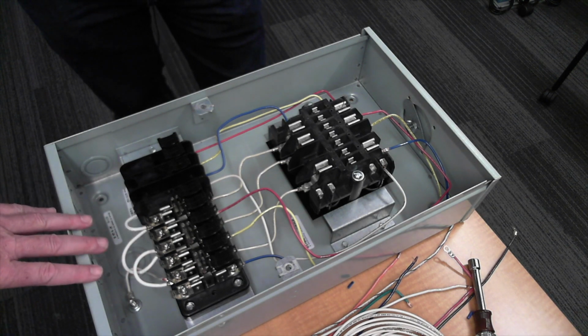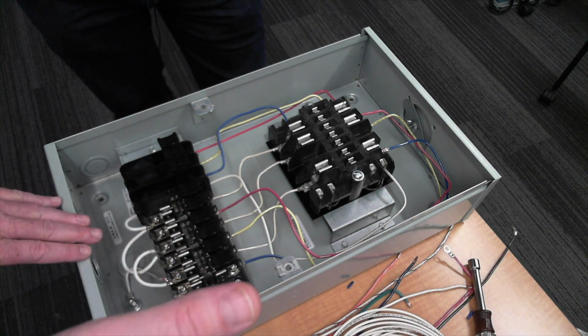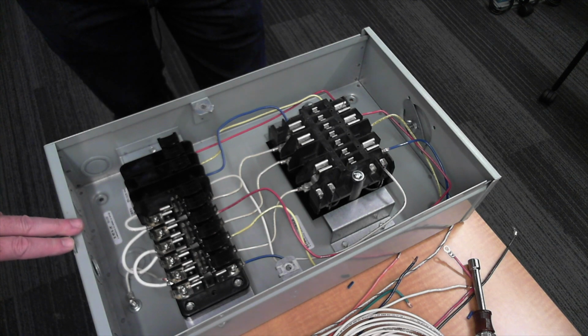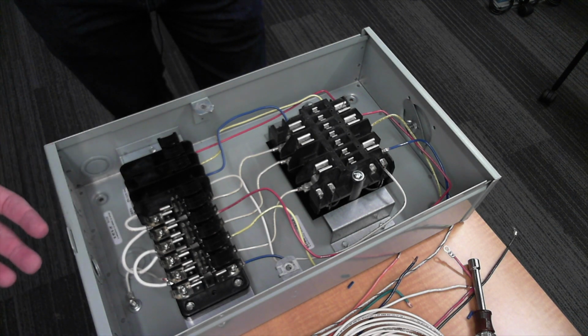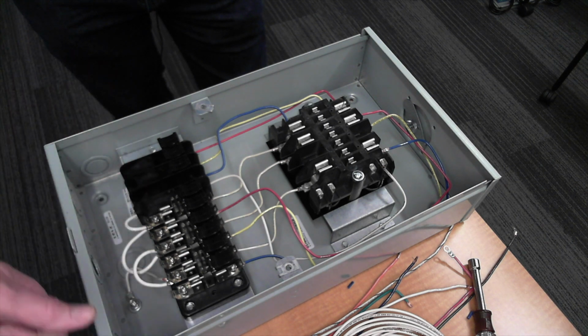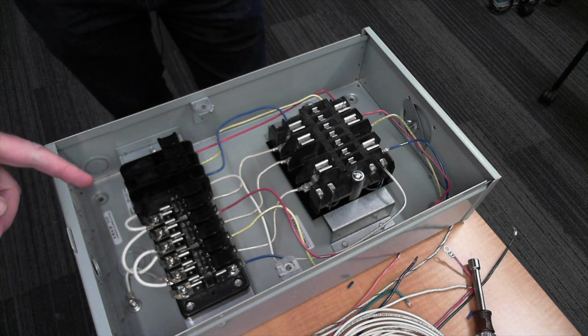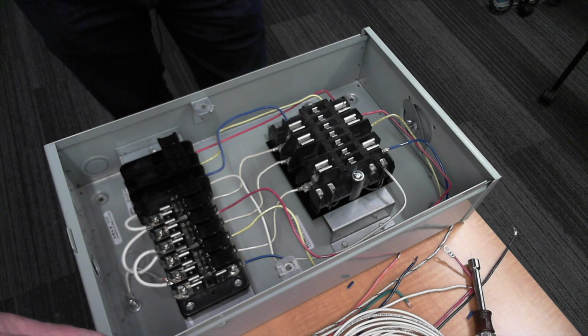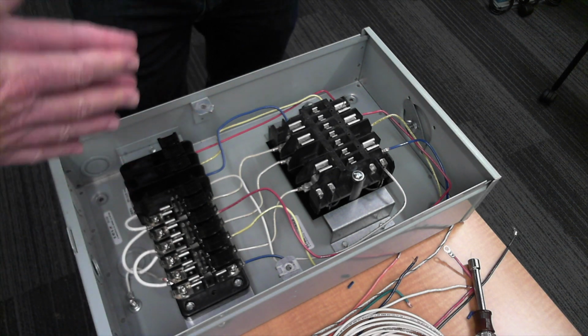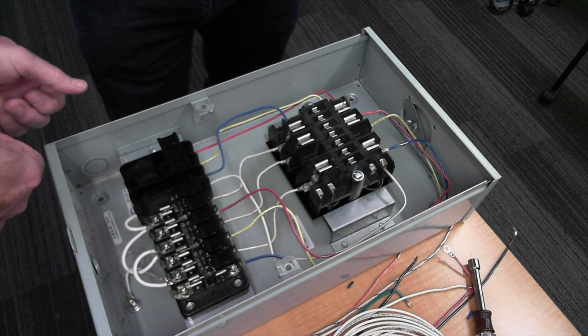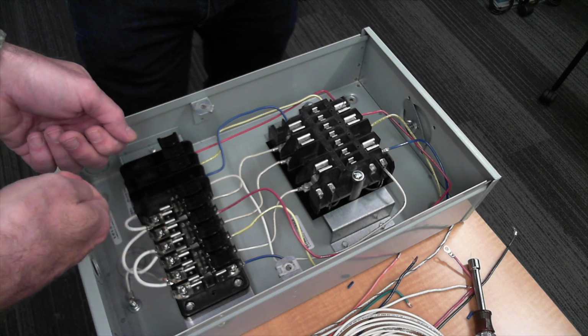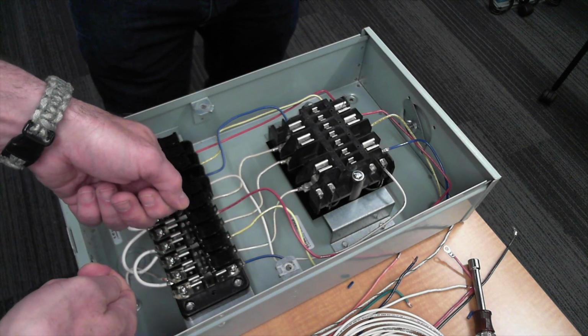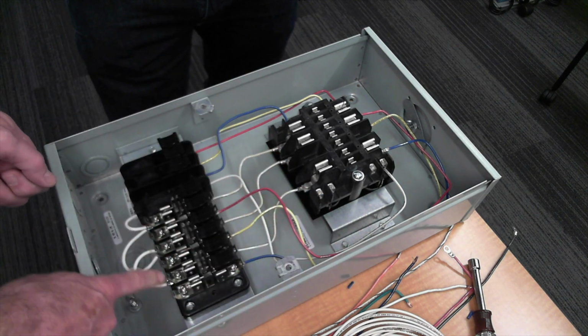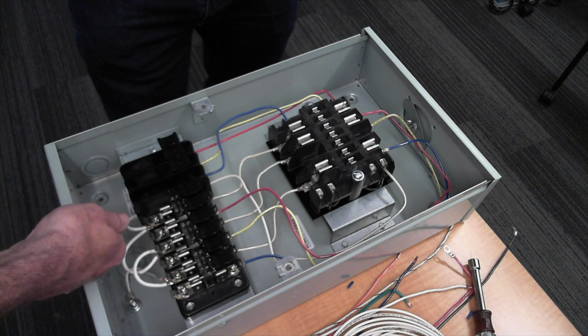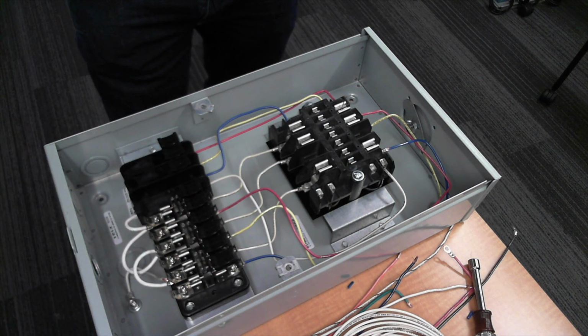Some people don't do that. They run separate returns for each one of their CTs, and we've talked about it in webinars. That means a little bit different on how you're going to do the testing. Like on a burden measurement test, you'd have to move it to pick up, because you're trying to measure out to the CT and back on each particular phase when doing a burden measurement on A, B, and C. So you'd have to move your neutral connection every time you tried to measure the burden on A, B, or C. But if they're tied together, I just leave them and make one connection and don't have to move it. Okay?